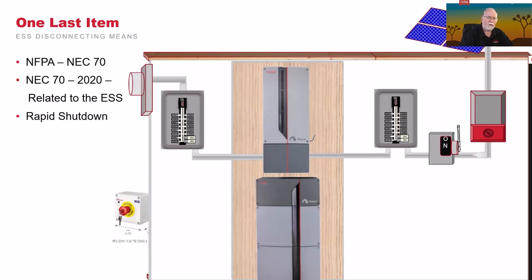One last item, NFPA NEC 70, the 2020 version changes some of the rules related to ESS and the requirements for emergency disconnect. So what I would suggest is that you leverage something inside the Mojave called the rapid shutdown. You have a couple of different options from Outback for rapid shutdown initiation devices, both our ICS and the IMO options. So if you note here, I have my disconnect in place. It's outside of the building, readily accessible. It's able to be locked out. I'll tie this into the rapid shutdown connections on the inside.